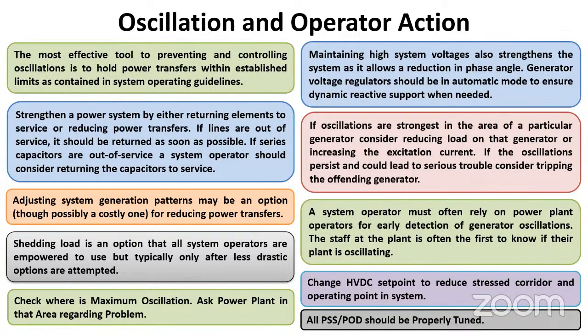And in those swings, this can result in a voltage issue at that particular node. There can be a protection operation, distance protection can operate. The voltage goes very low, or there can be a very high current, meaning high power going through those tie lines. So power swing and stability, all these things can happen due to that.